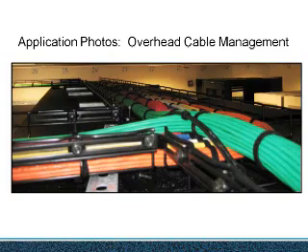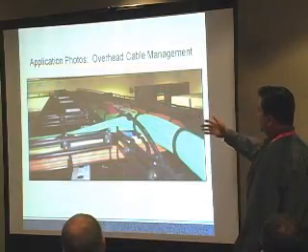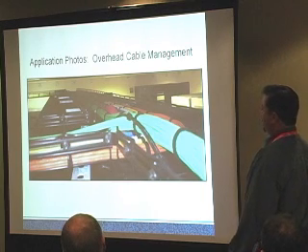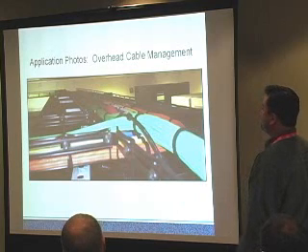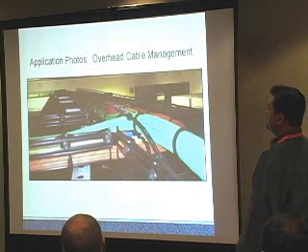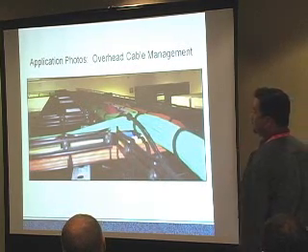And one more for cable management across the top. And this is actually a basket tray. And these are standard enclosures with the standard ladder rack type brackets, we'll call it. You can see by all that cabling, if that was all underfloor, how much it would impede airflows. Having it above is a benefit.